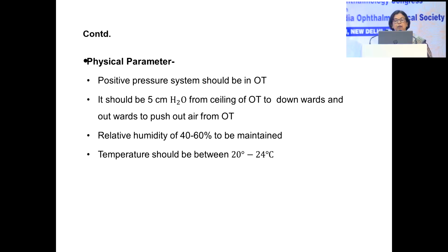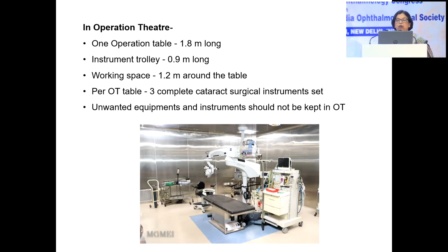It should be 5 centimeter H2O from the ceiling of the OT downwards and outwards to push the air out of the OT. Relative humidity should be 40 to 60% and temperature should be 20 to 24 degrees centigrade. In one operation theatre, one operation table should be 1.8 meter long, the instrument trolley 0.9 meter, the workplace around 1.2 meter around the table, and there should be 3 sets of surgical equipment per operation table. Unwanted equipment should not be in the operation theatre.